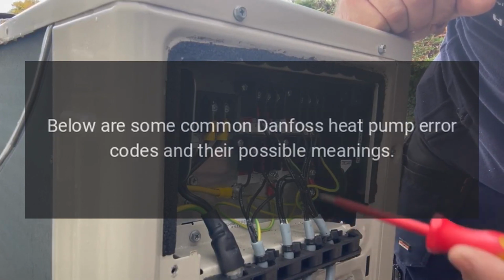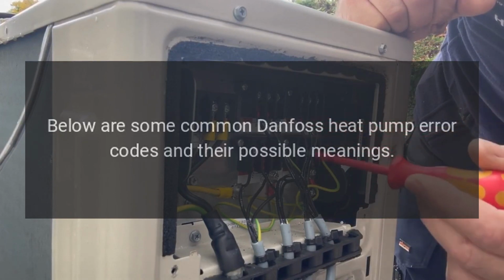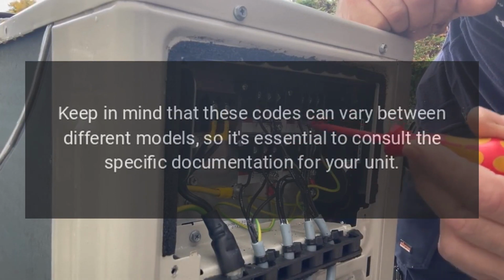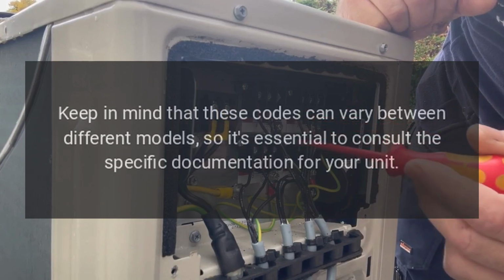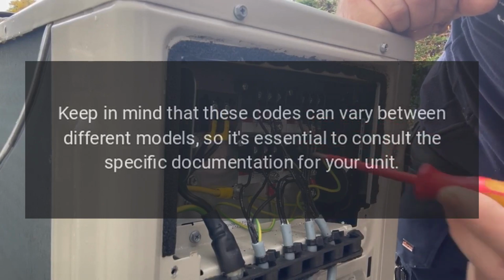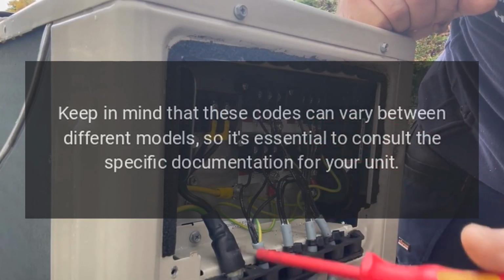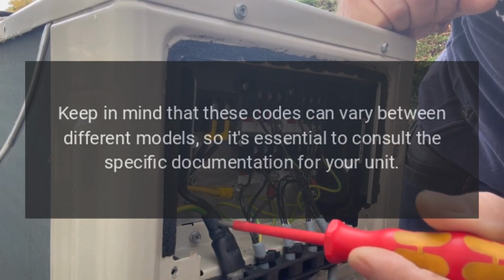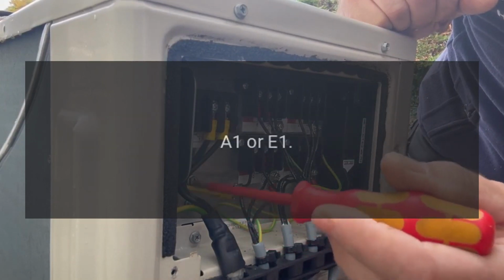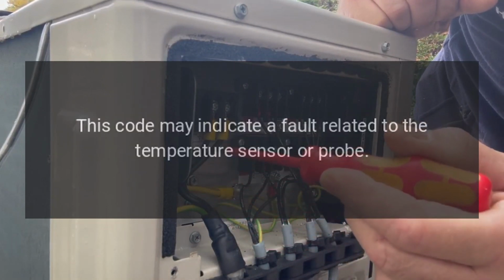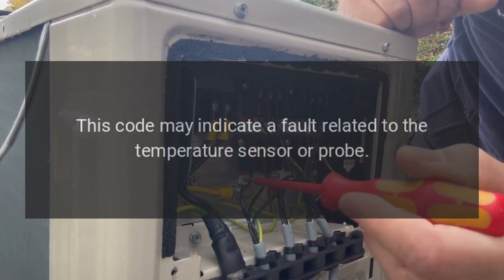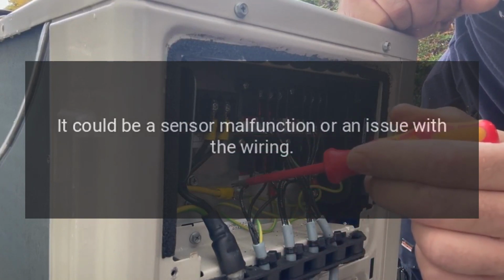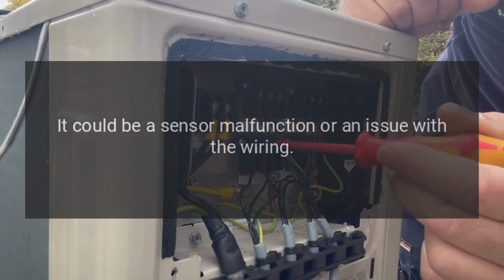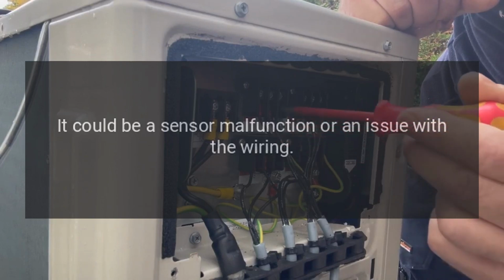Below are some common Danfoss heat pump error codes and their possible meanings. Keep in mind that these codes can vary between different models, so it's essential to consult the specific documentation for your unit. A1 or E1. This code may indicate a fault related to the temperature sensor or probe. It could be a sensor malfunction or an issue with the wiring.